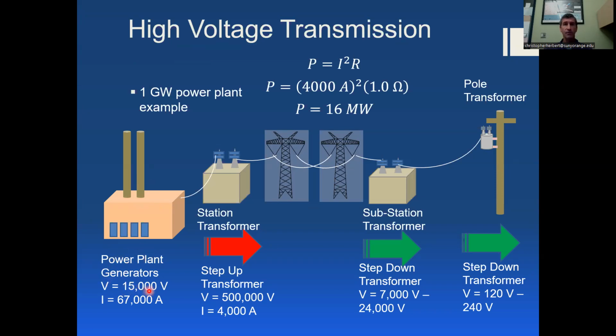Let's say that at a power plant, the generators produce power at 15,000 volts, 67,000 amps. If I put that straight on my high tension lines, that would result in a huge loss of power. You think about the power that you would actually lose, you'd end up probably losing more power than you'd actually deliver. But if we can boost this to a much higher voltage, remember, we're going from a primary with fewer turns to a secondary with more turns, I could go from like 15,000 volts to 500,000 volts. I drop my current. And if my total delivery transmission lines had a resistance of about 1 ohm, that would result in only 16 megawatts of power loss, compared to about 1 gigawatt or 1,000 megawatts of power delivered.